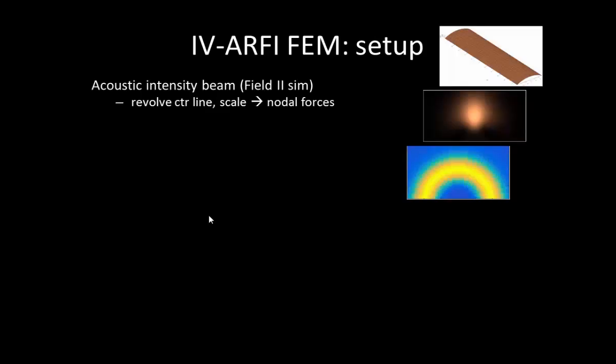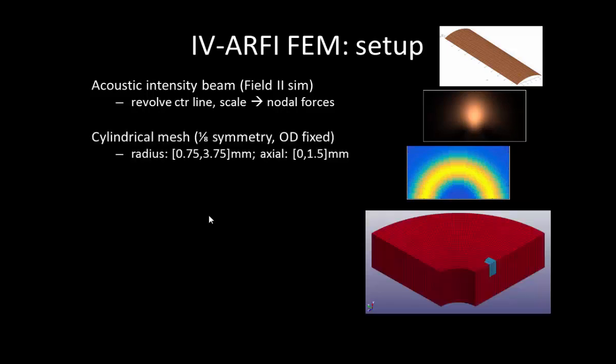We then investigated the tissue response using a finite element model. To set this up we first simulated the acoustic intensity beam profile using Field2. Field2 is limited in the angular extent of curved transducers it can simulate, so we simulated the beam from a sector and then took the center profile and revolved it about the catheter axis to get the beam shape that would be pushing radially outward in all directions, generating radial displacements. We then scaled the intensities found in this profile to nodal forces which we applied to a cylindrical mesh. The mesh was set up with one-eighth symmetry boundary conditions to reduce computational overhead.